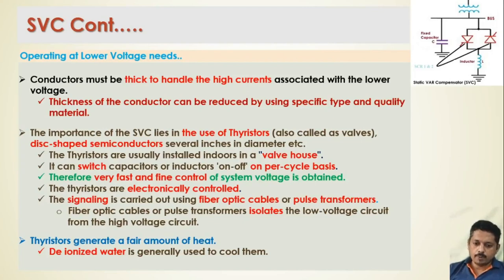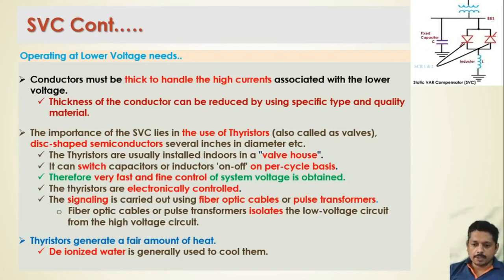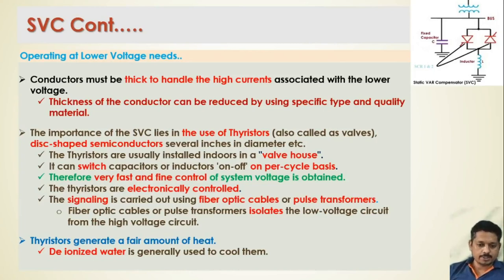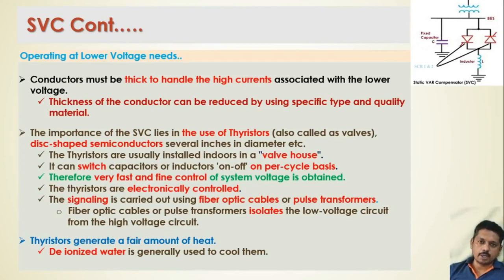Therefore, very fast and fine control of the system is achieved using these valves. Thyristors are electronically controlled, so operation is very fast. The control signal is carried via fiber optic cables or power pulse transformers. Fiber optic cables offer very rapid signal speed, while pulse transformers provide isolation between the higher-voltage and lower-voltage systems, giving rapid switching as well as protection for the lower-voltage side.